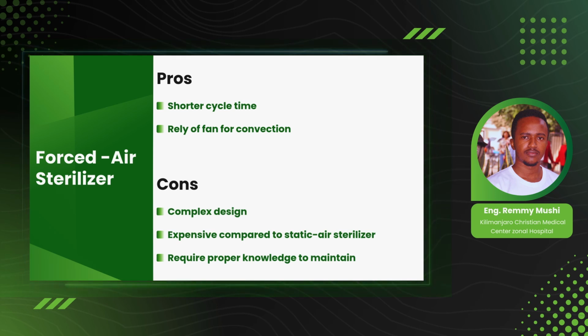The forced air sterilizer is a type of dry heat sterilizer which has the addition of a fan to counter the downside of the static air sterilizer. It can have a shorter sterilization time, or shorter cycle time. It relies on a fan for convection of the air inside the sterilizer, but due to the addition of technology, its complexity increases. There are additional parts, circuitries and sensors inside to ensure its functionality. It's also expensive due to the same addition of technology, and it requires proper knowledge on how to maintain it.